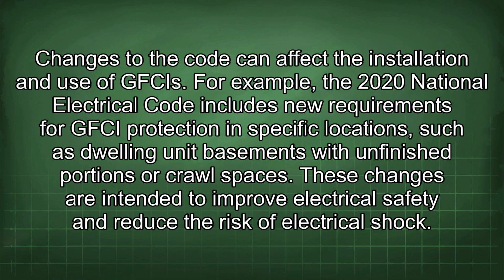Changes to the code can affect the installation and use of GFCIs. For example, the 2020 National Electrical Code includes new requirements for GFCI protection in specific locations, such as dwelling unit basements with unfinished portions or crawl spaces. These changes are intended to improve electrical safety and reduce the risk of electrical shock.